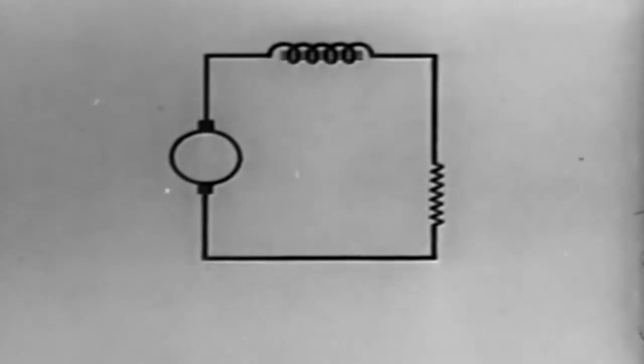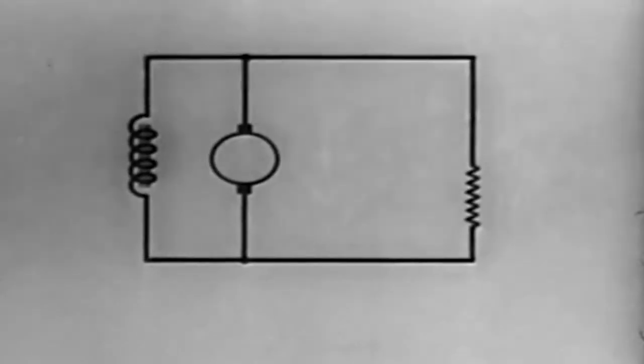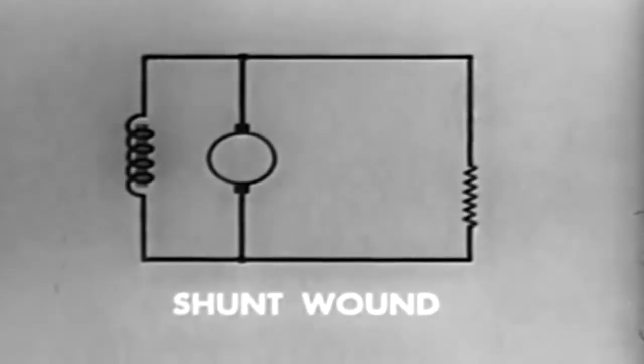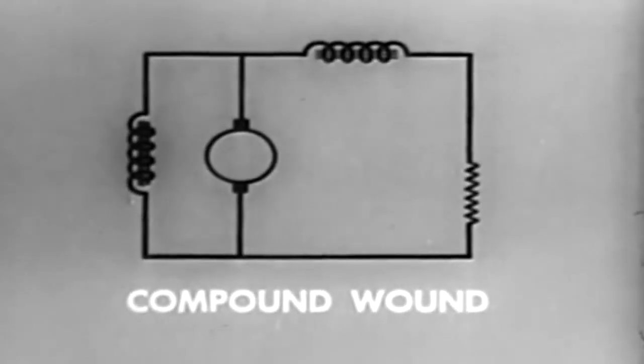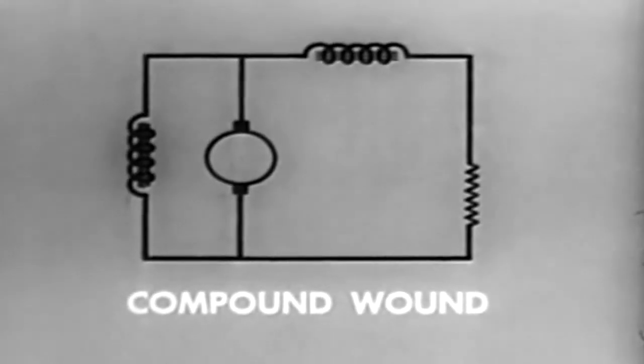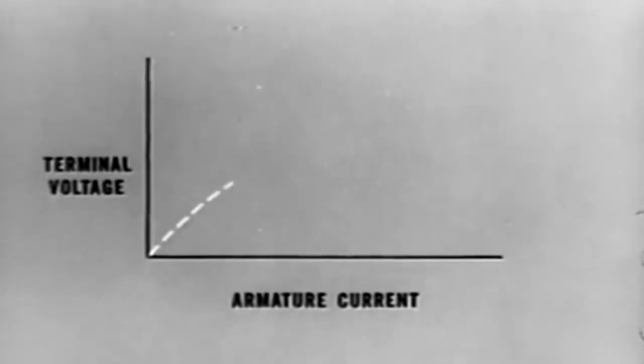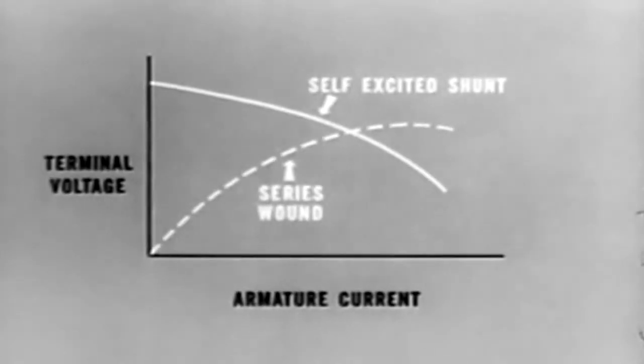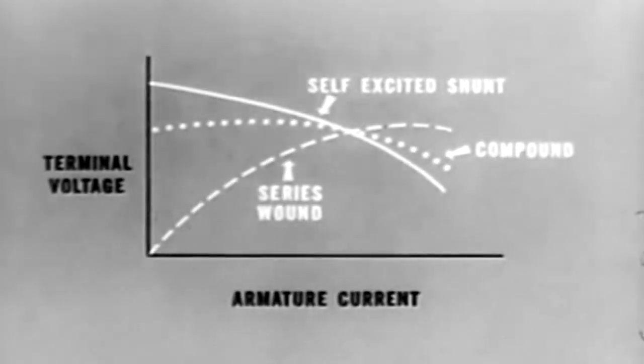Generator field windings are constructed in three ways: series wound, where the field windings and the armature are in series; shunt wound, in which the field winding is in parallel with the armature and the load; and compound wound, in which the best features of both the shunt and series wound generators are combined. Voltage regulation in the series wound generator is poor. In the shunt wound generator, voltage regulation is fairly good, but current regulation is poor. Compound wound generators provide stable voltage under changing loads — this output is normally most desirable.